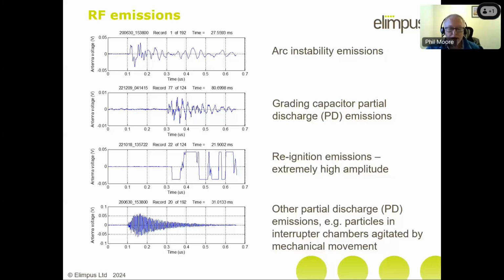The third signal here is a reignition transient, a radio frequency transient. Again, that's quite low frequency, but it is extremely high amplitude. Even a tiny reignition will cause our system to clip. So they're very, very easily understood. They shouldn't be there. In an ideal world, you should never see a reignition transient on a circuit breaker. But if you do get them, then that's one of the ways you'll know that you've got it.